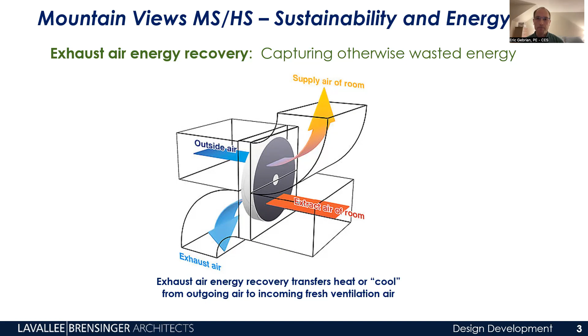The warm air leaving the building warms the wheel as it rotates, passing that heat to the cold air coming in, in the example of winter. You can save 70 to 80% of heating just from this one technology, which uses very little energy. That's what we're doing on the ventilation and exhaust side for the entire school, saving a big chunk of energy.